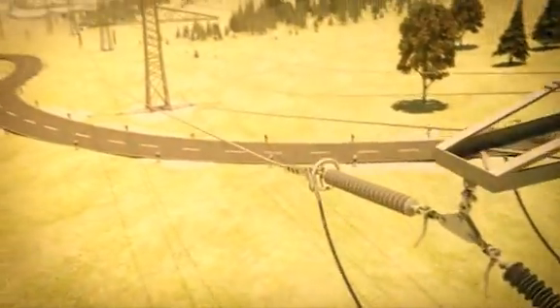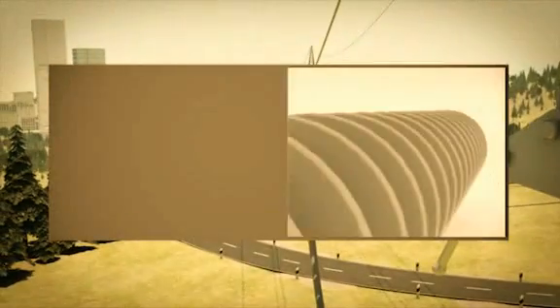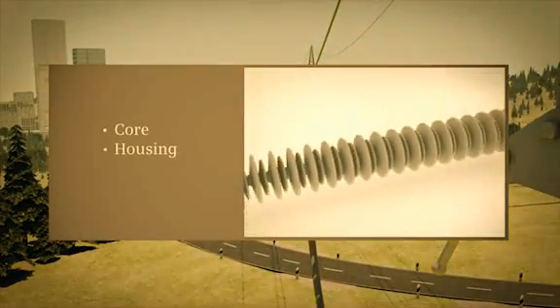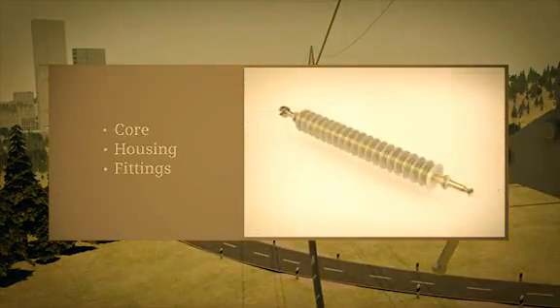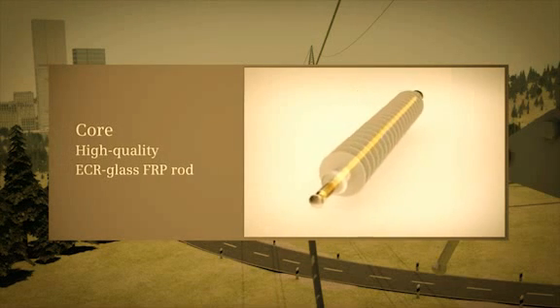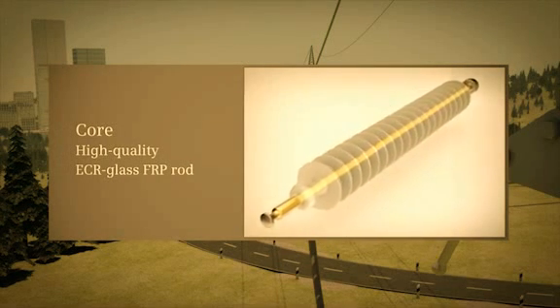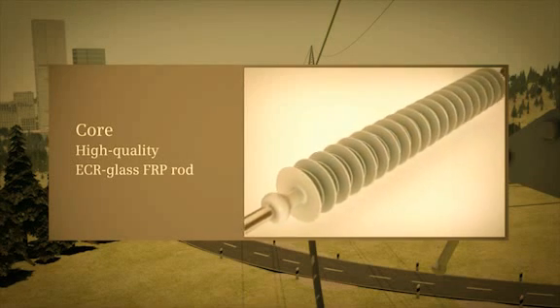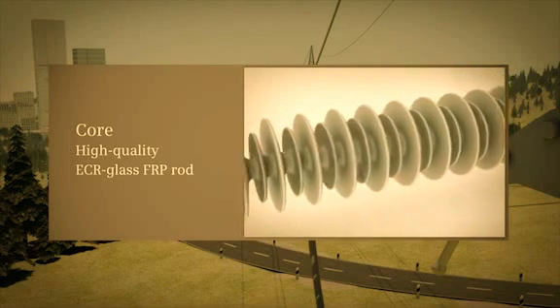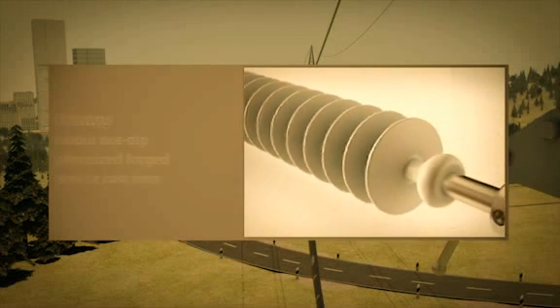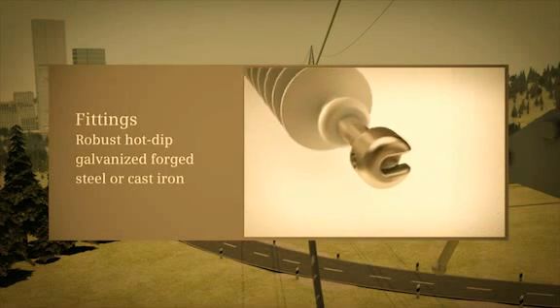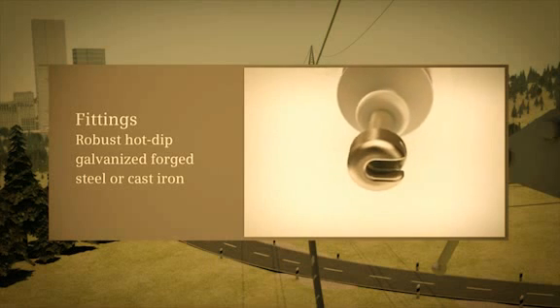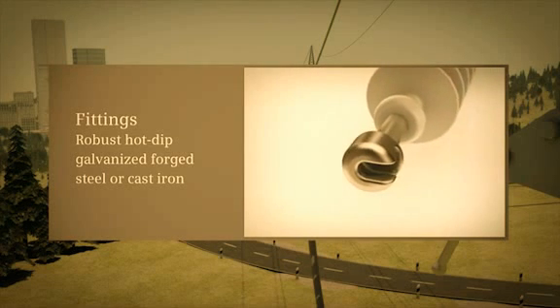They consist of three key elements: the insulator core, the housing, and the end fittings. The core of the insulator is a high-quality ECR glass FRP rod. This core is housed in a one-piece HTV silicone housing, which is directly molded onto the FRP rod. The metal end fittings are made of extremely robust hot-dip galvanized forged steel or cast iron.